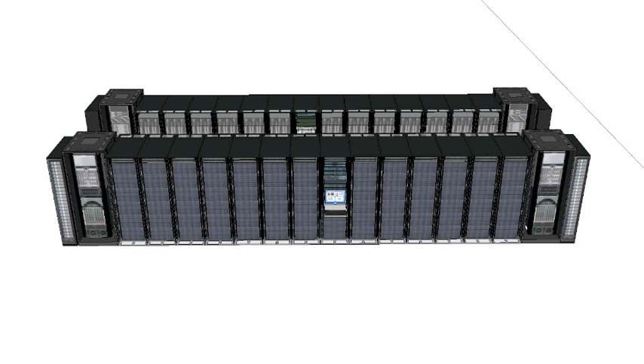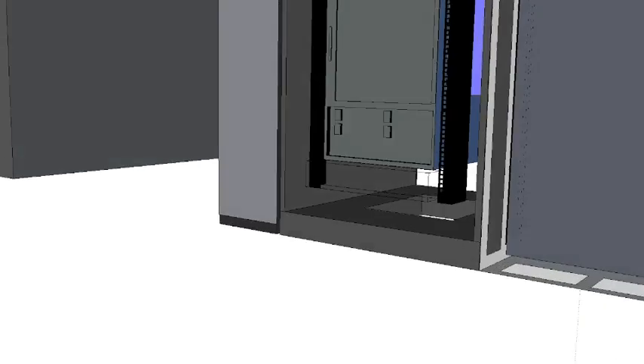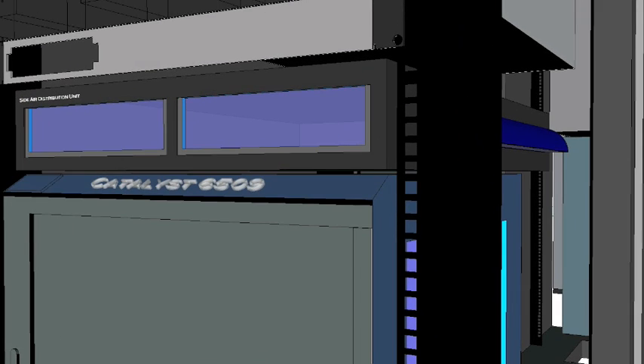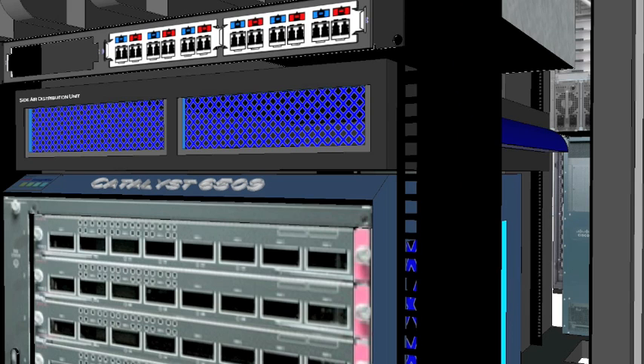You may notice that some of our switches cool side to side. We do this for port density reasons. And you may have a challenge in structuring an energy efficient airflow with your cooling system because of these disparate airflows, with the servers going front to back and the switches going side to side.